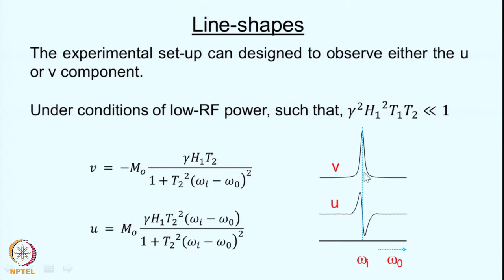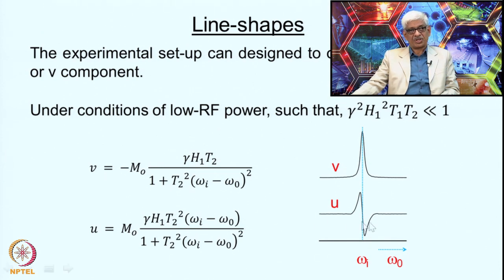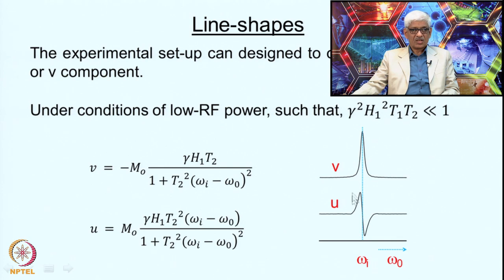Typically the absorption line shape is used for NMR spectra. The dispersive line shape is used for monitoring field drifts, especially for locking purposes, because it is easy to see deviation from the resonance condition — at resonance the dispersive signal is zero, and any deviation produces a correction signal for the spectrometer. The absorption line has a nonzero integral whereas the dispersive line shape has a zero integral.